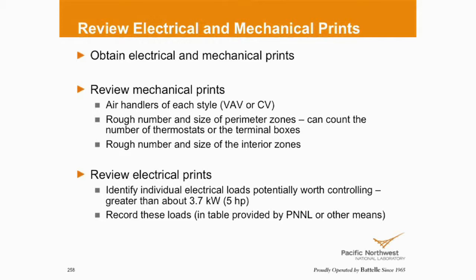You know, is it a good design? Am I zoned properly? Do I have systems that are feeding an HVAC system that's feeding both perimeter and interior zones, which becomes problematic? Do I have an HVAC system that's serving a corner office and then a bunch of other offices? Corner offices are problematic because of the exposure, generally to at least 2 exposures. There may be other things that you identify on the mechanical prints that you weren't aware of yourself that the engineer did. If it's an older building, a lot of times you find opportunities. And as I think of them, I'll throw them out.